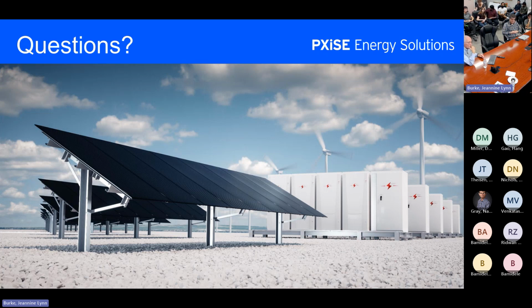Okay. This is a very specific one. It's asking about the ROCOF. Yeah, go ahead. So the summary of the question is that normally, let's say the load in the microgrid is consuming 1 megawatt, and the generators in the microgrid are even 500 kilowatts and you are importing 500 kilowatts. In that case, the import is tangibly high. And when there's a fault upstream, like a fault on the main grid, and the recloser at the substation opens up, the law says that your own breaker at the POI should also open up so that you are not backfeeding the load.